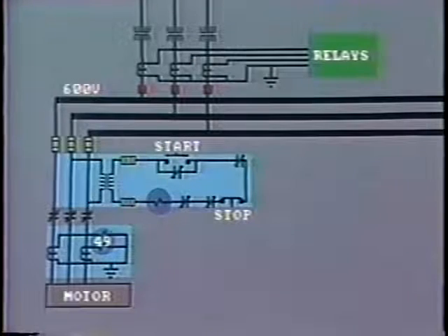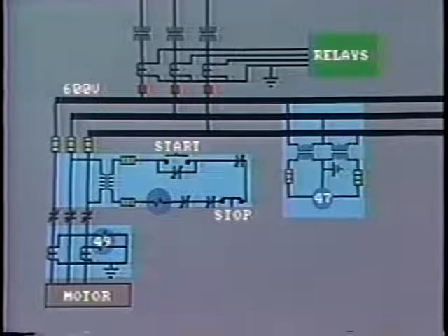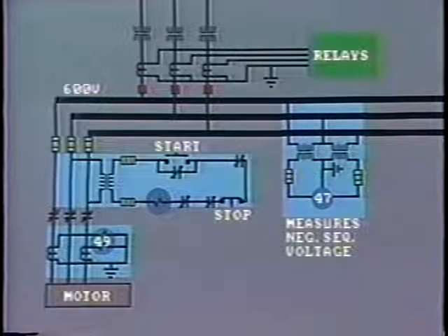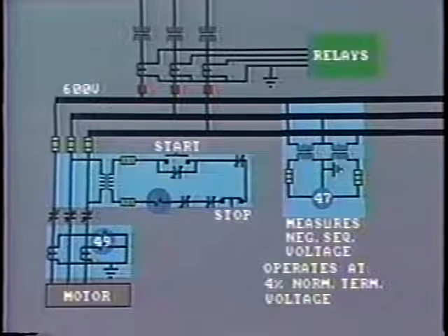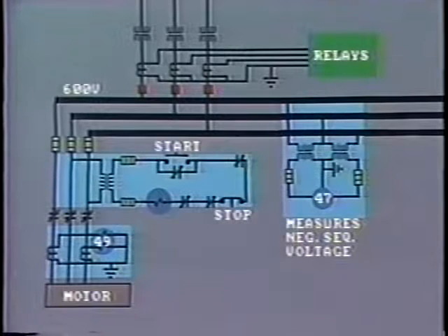We know that overload causes overheating, but overheating can also be caused by phase unbalance. Protection is often provided against unbalance by the installation of a negative sequence overvoltage relay, 47. This is connected to the bus to measure the power supply conditions. The relay is connected to measure negative sequence voltage only. This is normally 0 or at least very low under balanced conditions. The relay is set to operate at quite low voltage when negative sequence voltage rises to, say, 4% of normal terminal voltage. When the relay operates, it trips all of the motors on the bus.